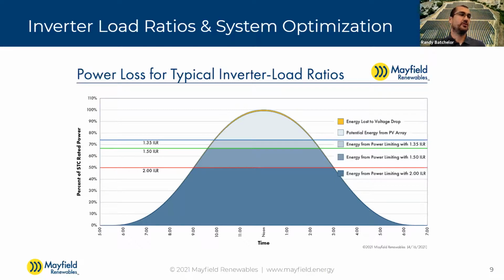From a practical perspective, really what you're doing is just loading the inverter up for more hours of the year, and having the inverter operating at full throttle, full capacity, which just stresses the components more. So it's more of a longer term look at - now you have these electronic components under full load, fully stressed, running hot for more hours a year. And so how does that affect the 10, 20-year outlook for how long this inverter is going to last, and the inverter warranty? That's where it starts becoming an issue for the inverter manufacturers, and they're starting to look at it in a more sophisticated way.